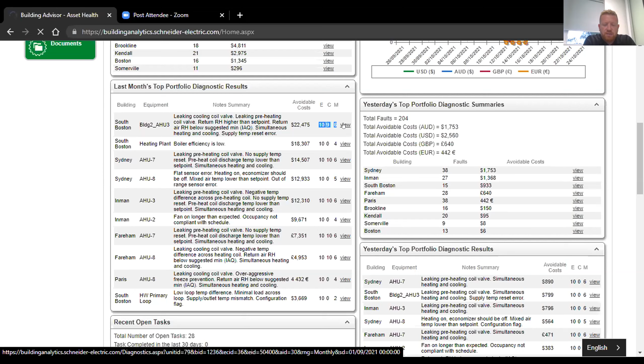In this case, we have the mechanical assets with a summary. As a user, you'll be able to see the building automation or building management system points that we're monitoring - temperatures, status, occupancy, fan speeds, flow rates, so all the BMS data.